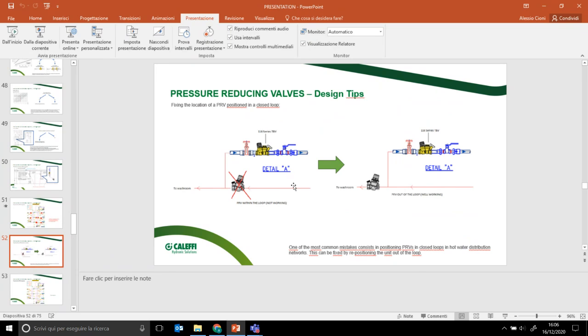So if you install it in a closed loop, and the closed loop is pressurized, it is a closed pressurized system. So the pressure set value is always reached. It means that the tendency of the PRV in the closed loop will be to stay closed, so to obstruct the normal water flow. That's why this position is absolutely not good. But also if you put it here, it will not be good. It has to stay out of the recirculation loop.